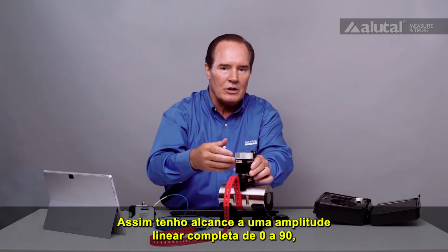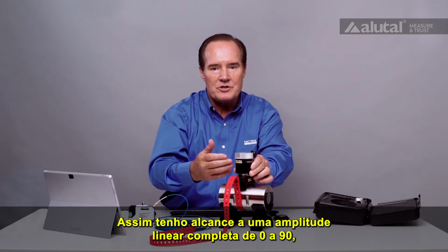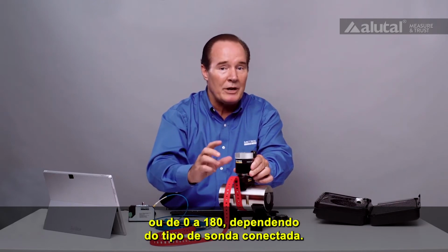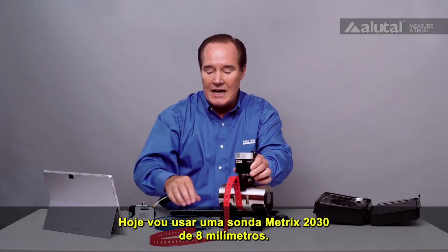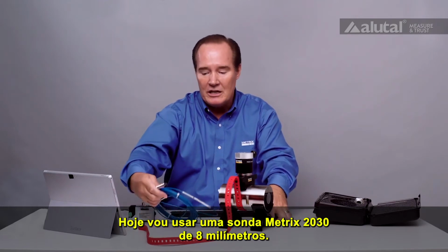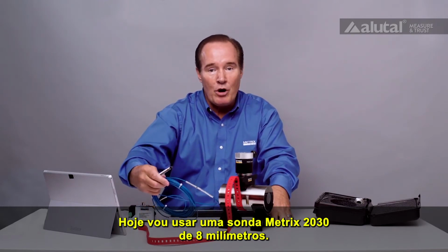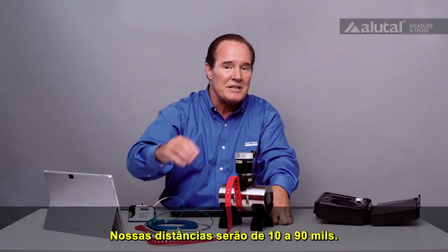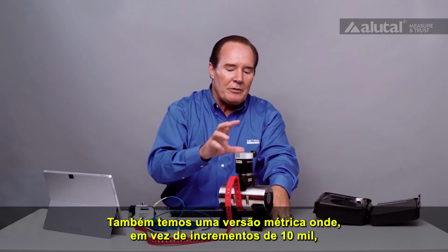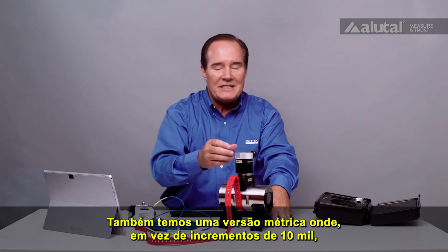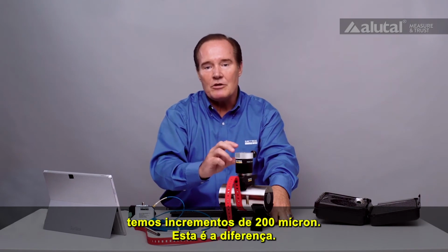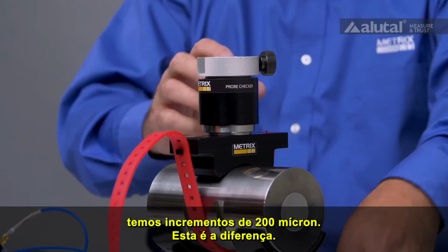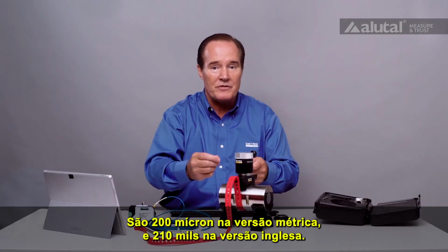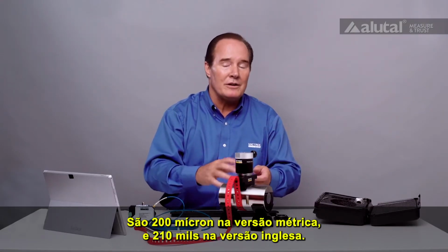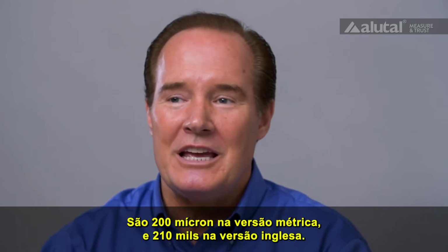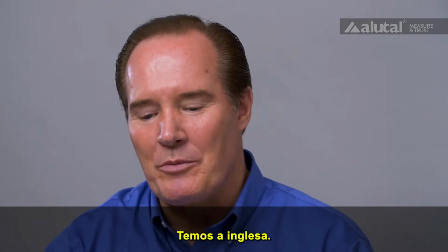So I can get a full linear range, 0 to 90 or maybe 0 to 180, depending on what type of probe I have in. Today I'm going to be using a Metrix 2030 8mm probe, so we're going to be looking at distances from 10 to 90 mils. We also have a metric version of this. Instead of 10 mil increments, it goes in 200 micron increments. So that's the difference: 200 microns for the metric version, 10 mils for the English version. So that's what we have.